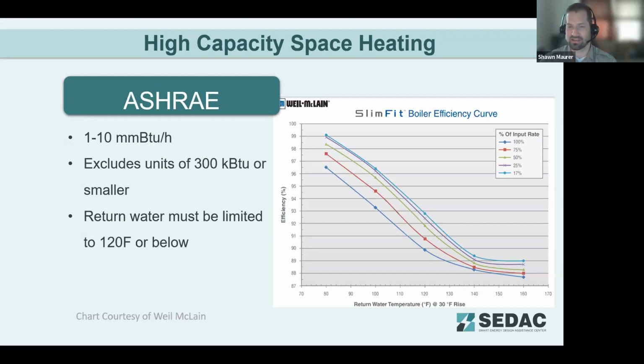So the chart we've included here just shows that efficiency change with the return water temperature at a 30-degree Fahrenheit temperature rise in the boiler. And so what ASHRAE has included here are requirements for the design of the system where the return water temperature is going to be limited to a temperature that's going to allow condensing to happen at the boiler still. So these are things that are good practice that ASHRAE is now mandating, where the IECC is allowing those things to remain as standard practice, but isn't really mandating them yet.